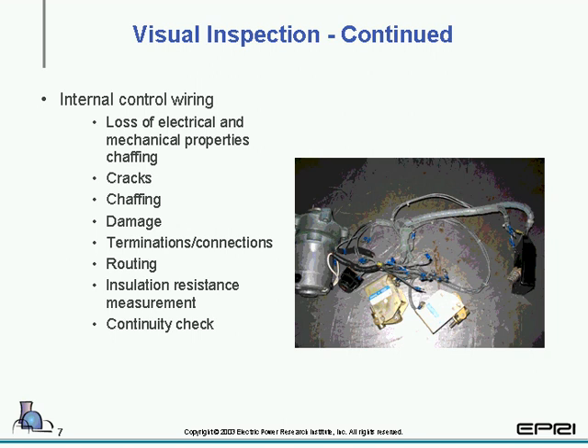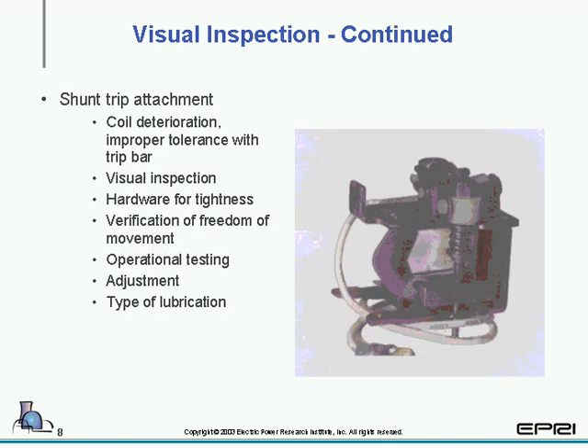Internal control wiring. Along with the list, most electrical components cannot be visually seen if they are bad. You must do some sort of testing to verify their operability. One of the key important ones is the shunt trip test. So we're going to spend a little more time taking a look at that along with a more detailed list of what you're looking at. But again, your shunt trip, this component, cannot just be visually inspected to verify the condition.